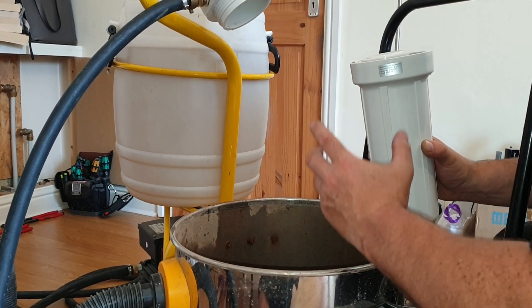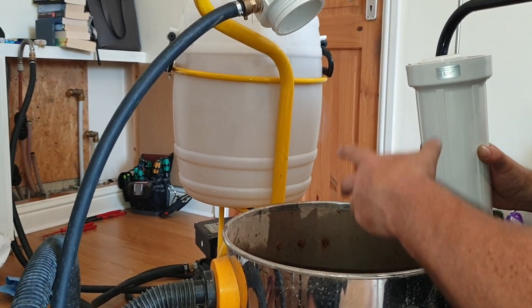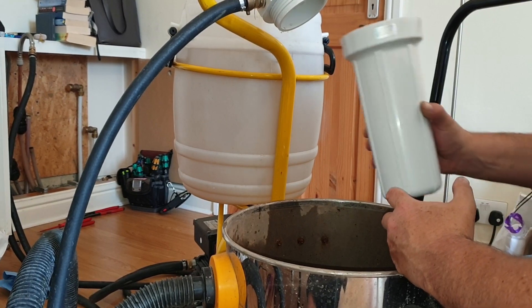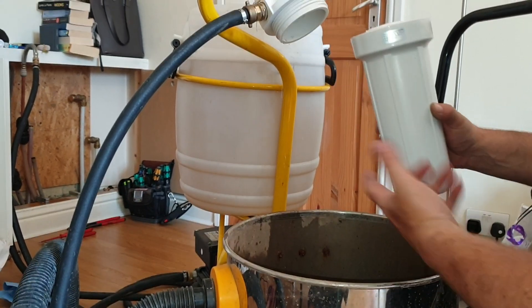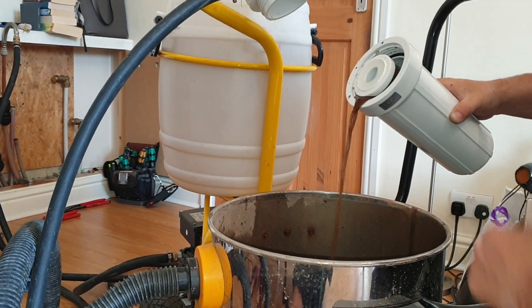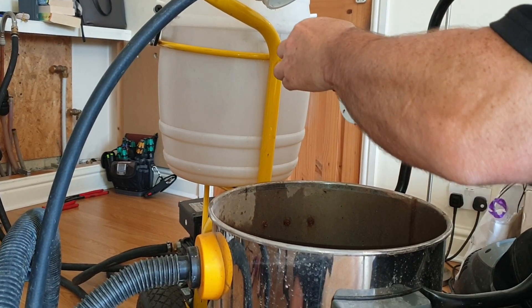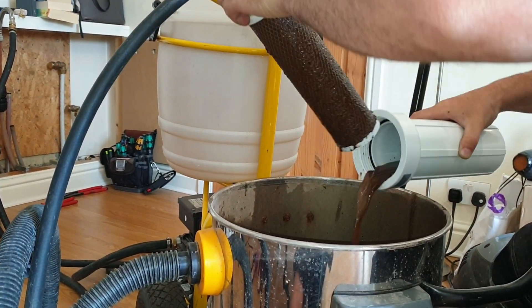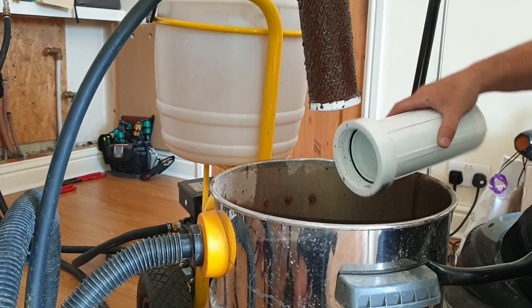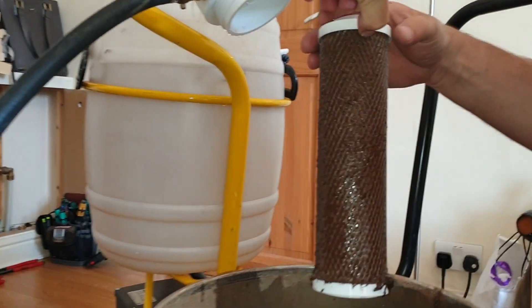We wanted to try a different method of flushing out this underfloor heating circuit. It's the non-barrier type — it blocks up over years and we want to retain the chemicals. So what we've done is we've just rigged up this inline filter. It's just a normal water filter, and you can see we've just done one circuit, but look at what it's caught — come up close and have a look at the bottom.